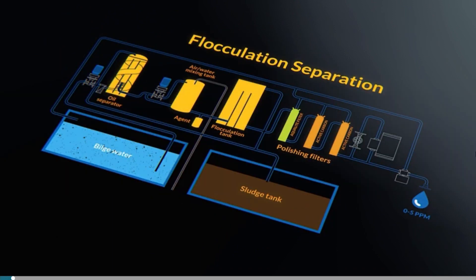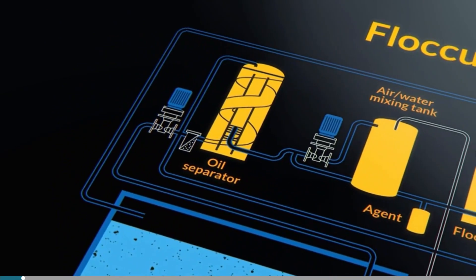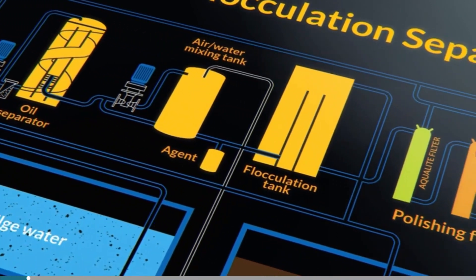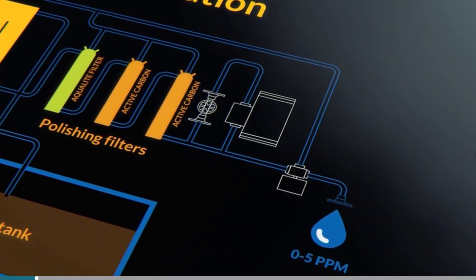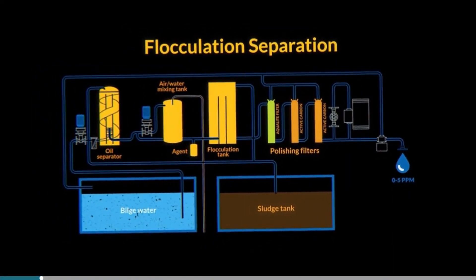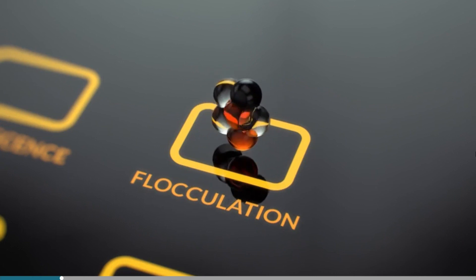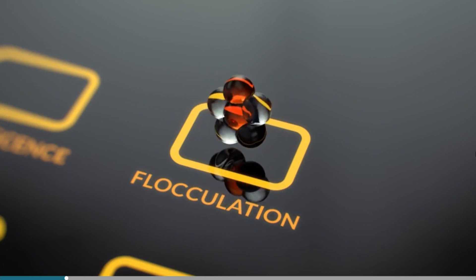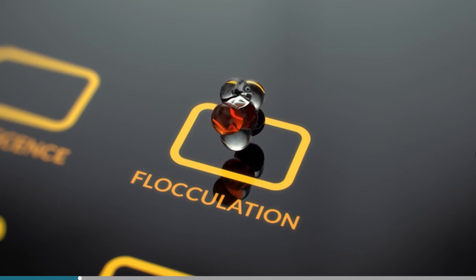In this chapter, you'll learn about the working principles of flocculation and the main components of a flocculation-type bilge separator. Bilge water separators using chemical flocculation are claimed to be the most efficient and are one of the most popular types, so pay special attention to this chapter. Flocculation is a process in which two or more particles aggregate and stick together. In the well-known Marin Flock AB system, we help the flocculation process along by adding a flocculating agent, such as polyaluminium chloride, to the bilge water.